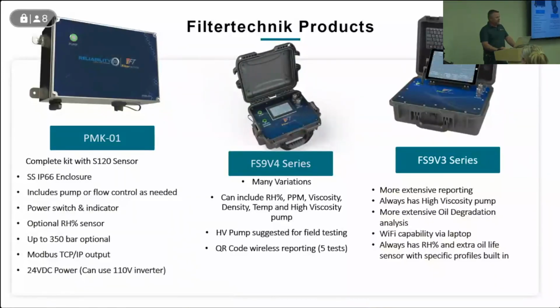So you have a display, and then you have the fluid ports directly on top of the device there, so that, let's say you want to go out and collect a sample and run it back in your lab, you can run it directly there at your office and run a quick sample. So the standard devices do all the standard oil wear particulate analysis, but if you wanted to add moisture, either in ppm or relative humidity, you have the ability to do that. And there are also some different types of pumps you can add if you're trying to run a highly viscous type fluid. I know it's one of the questions you had asked earlier.